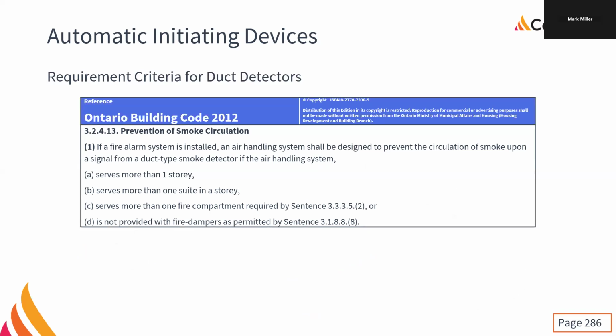Where do we install them? Well, an air handling system is going to be designed to prevent the circulation of smoke upon a signal from a duct type smoke detector if the air handling system serves more than one story, more than one suite in a story, more than one fire compartment, or if it is not provided with fire dampers.